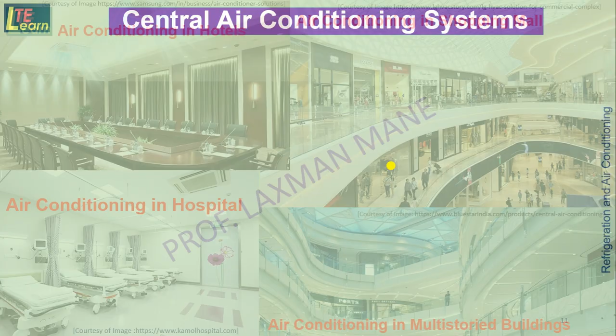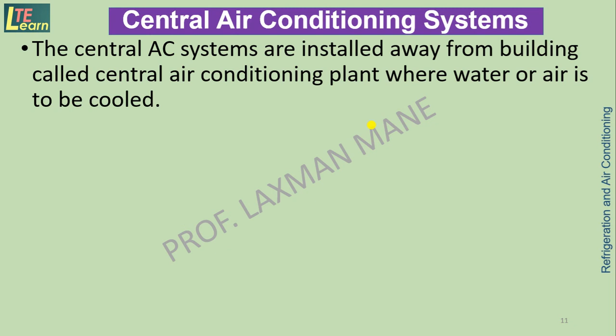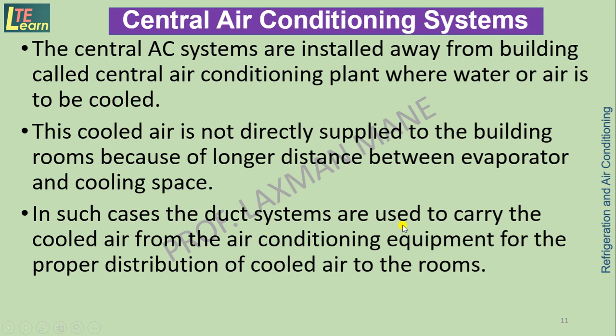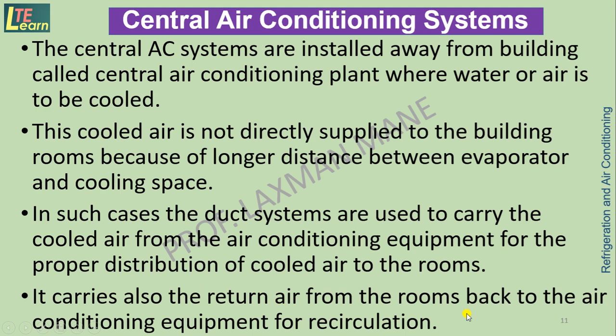The central air conditioning systems are installed away from the building, called the central air conditioning plant, where water or air is to be cooled. This cooled air is not directly supplied to the building rooms because of the longer distance between the evaporator and cooling space. In such cases, duct systems are used to carry the cooled air from the air conditioning equipment for proper distribution of cooled air to the rooms. It also carries the return air from the rooms back to the air conditioning equipment for recirculation.